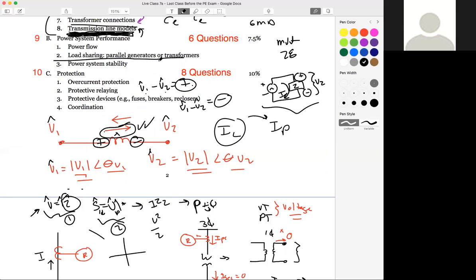Protection, we talked about this. We did a really good overview on that, but remember zones of protection, you kind of think of it as Venn diagrams, right? If you've got a fault in a zone of protection, any breaker within that zone will trip. And you also have the likelihood of having overlapping zones, right? You might have breaker 1 in zone 1 and 2. So if you've got the middle of a Venn diagram, where you have two circles overlapping, then if you have a fault, it could potentially exist in more than one zone.